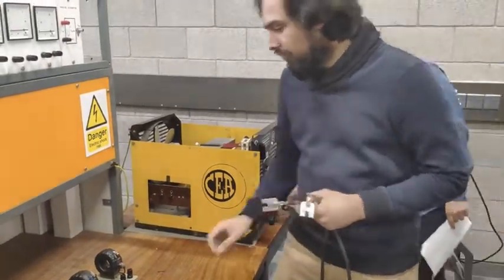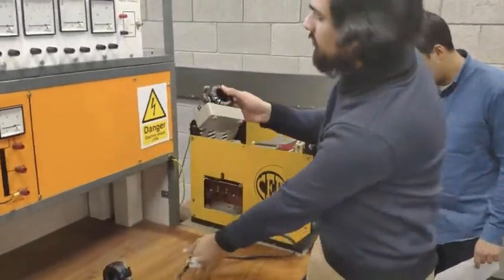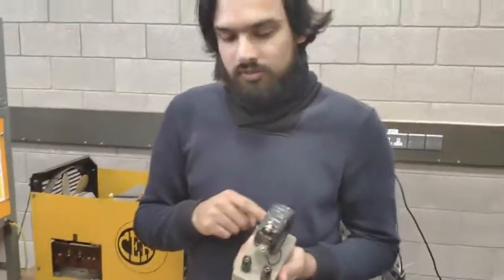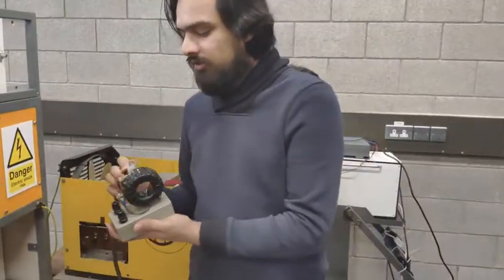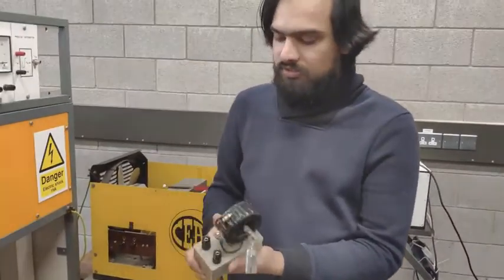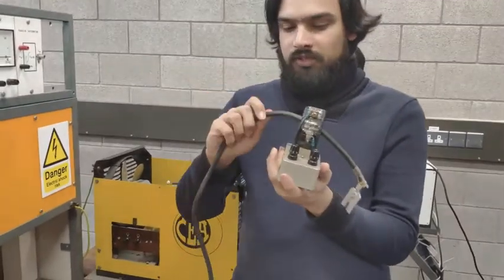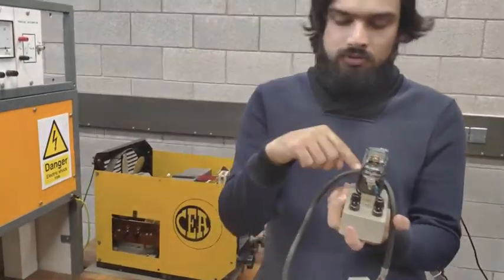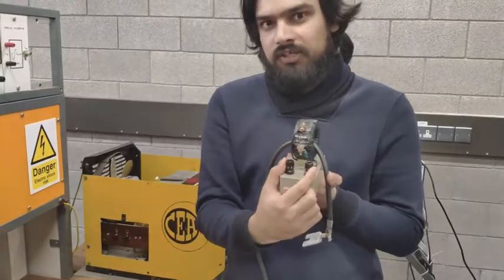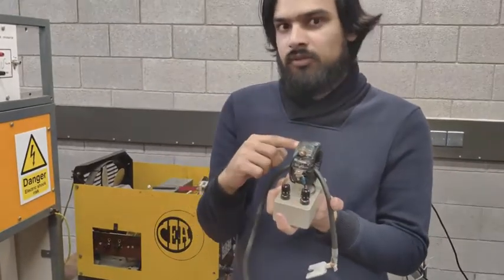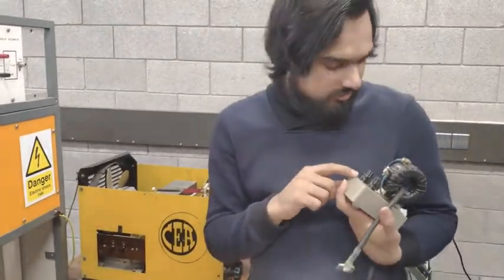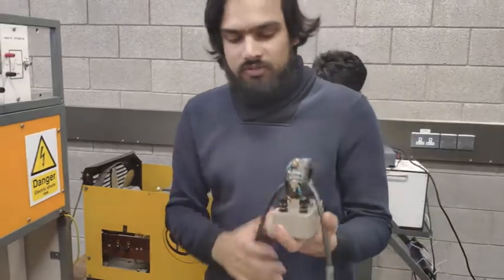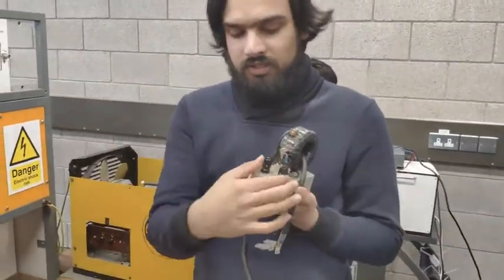And before I use that, I should tell you that this is a current transducer. If I make a turn here like this, this will be my primary side of the transformer, and then this will be the secondary side. So this will step down the current, and it's rated 120 to 5 amps. If I have 120 amps here, I can get 5 amps here.